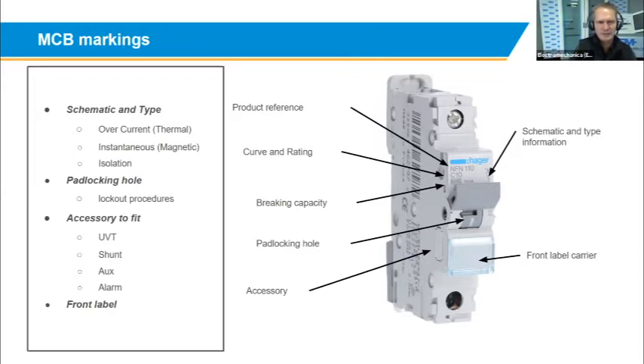So again, if you look at the SANS 10142 standards for South Africa, which is the installation regulations, it states that in a distribution board, the main incomer must be able to do isolation. So the first breaker in your DB is supposed to be an isolator, but having to put an isolator and then a circuit breaker actually defeats the object. With the Hager product, because it does the isolation function, you can use a Hager breaker as a main incomer with isolation, overcurrent and short circuit all in one product.